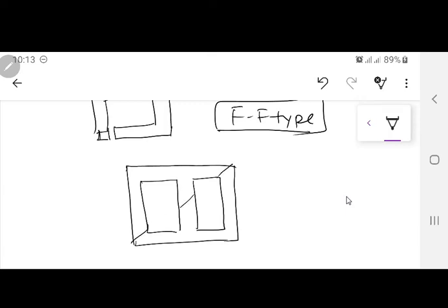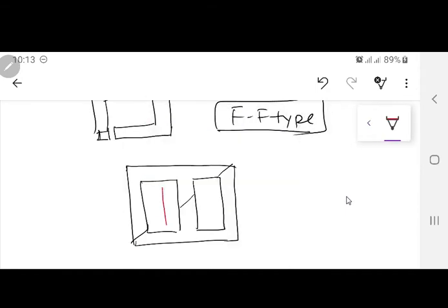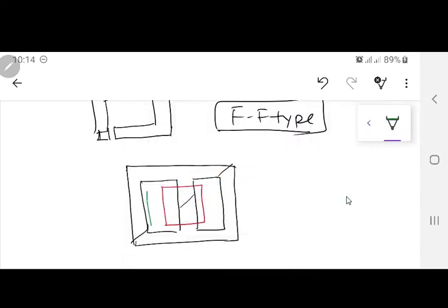So actually, where do you have to make the windings? You have to make the winding on the central limb. Low voltage winding first, and then afterwards the high voltage winding. I am not going with the sandwich winding. I am going with the radial winding or the concentric winding. So now how do you have to make this winding? You will make this winding separately beforehand, and then afterwards each lamination is going to be stacked together.